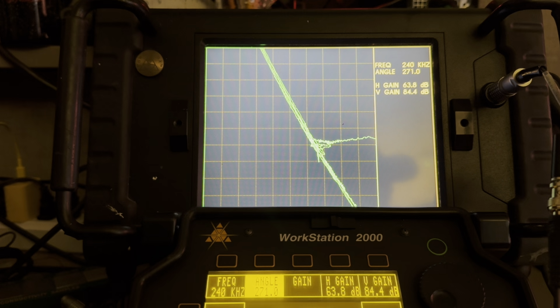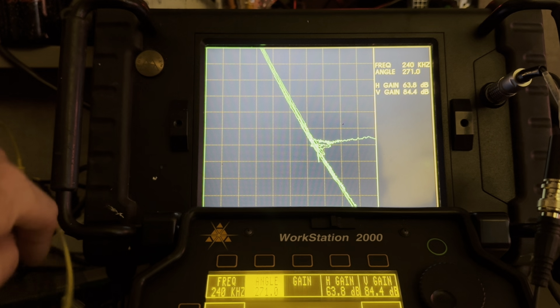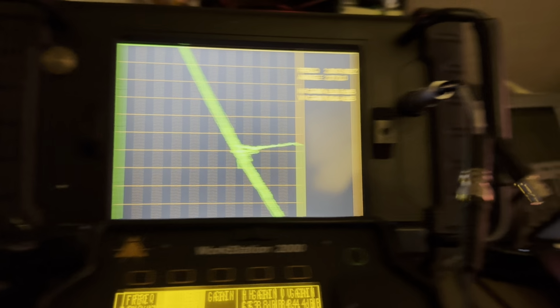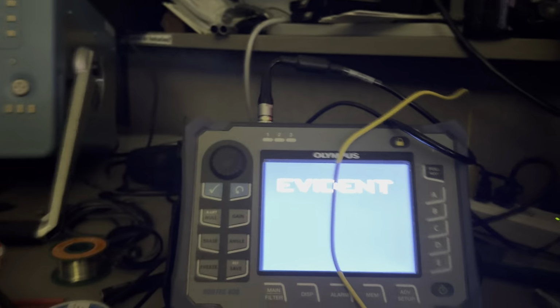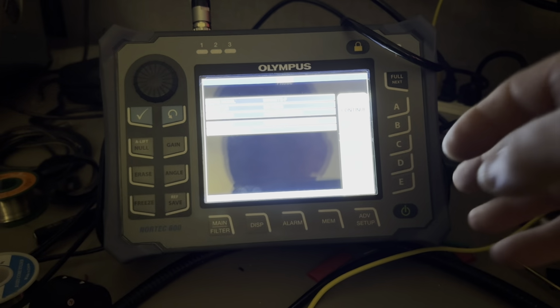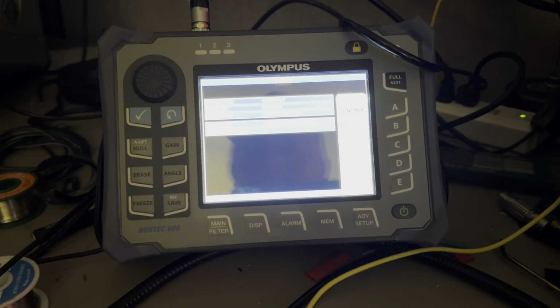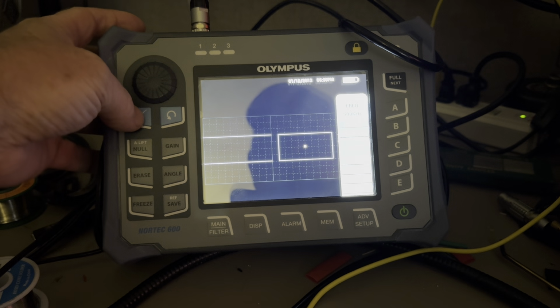So now we're going to switch our focus over to the Nortec 600 and power that baby up. Sorry for the adjustment. This is what you call logistics. What's called training logistics, right? So we've got the Nortec 600, and like most modern instruments, it's got a chip built into the scanner and the probe. So it automatically recognizes I'm using a mini-mite scanner. Yes. Probe serial numbers on there. Reflection differential. Okay. So that's going to have some self-canceling attributes to it, make our data cleaner. So I'm going to hit A for continue and then hit the little check mark.